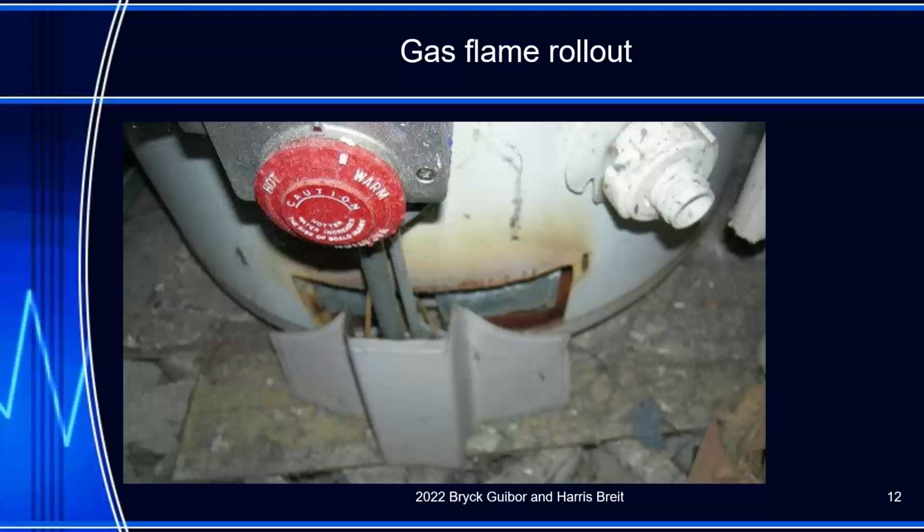This is for a water heater. Harris, is this old? It is old and backdrafting. Yeah. So here you can see the burn mark in the front. So on new water heaters that are vapor resistant, would I ever see back venting? What's that now? No. Yeah, it's a trick question. You'll never see back venting on a vapor resistant water heater because there's no opening to the gas. It has a little window on it. I hate these things because you can't tell if you're lighting the pilot or not, the piezoelectric. So older water heaters have back venting. Newer water heaters will never have that, except up at the hood.